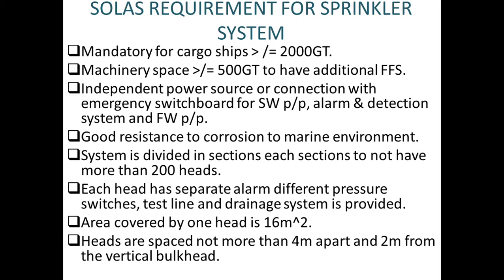So in order to maintain that pressure, we divide it into sections, and we have 200 sprinkler heads in each section. Each section has a separate alarm, different pressure switches, a test line, and a drainage system is provided. We are draining because if the ship is in a colder region or colder climate, there is a chance that the water in the pipeline will freeze. We'll talk further later about anti-freeze, dry pipe system and wet pipe system, but we have a fixed drainage system for that.